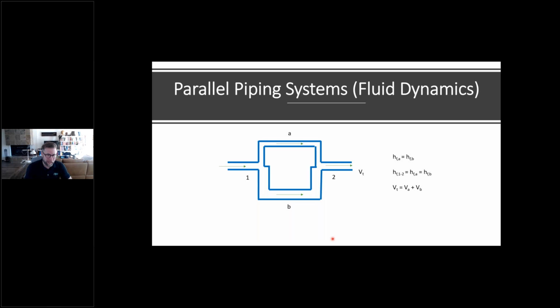The two other ways that a lot of my audience members typically suggest for increasing the flow through A would be by putting a balancing valve on B, restricting the flow, and thereby creating, in your mind, an artificial pressure drop in B through that balancing valve, and that would promote more flow through A. Or you could potentially put a pump on A to push that water through.